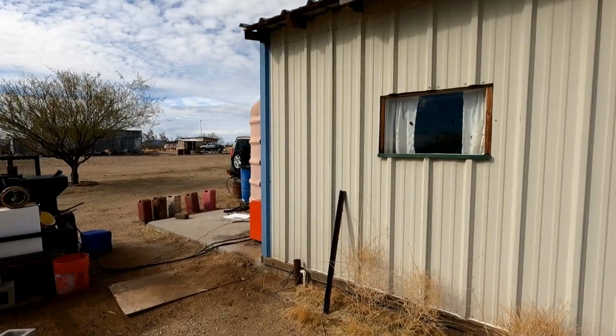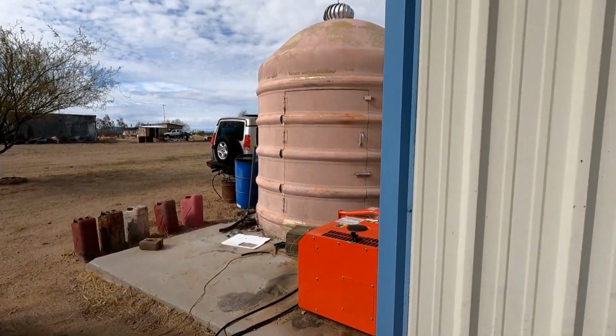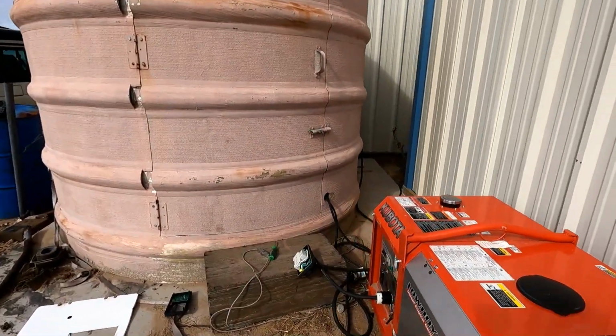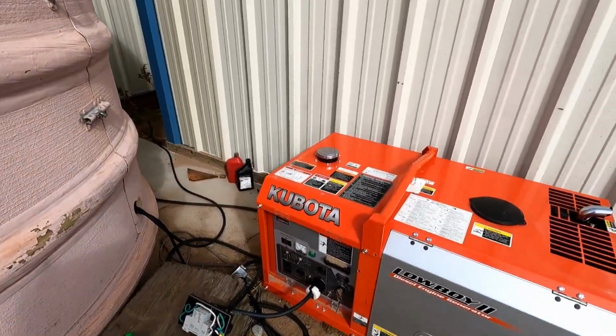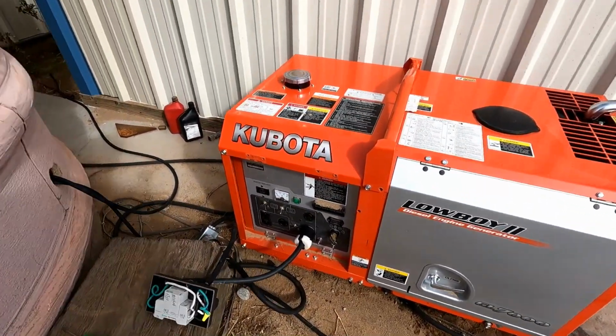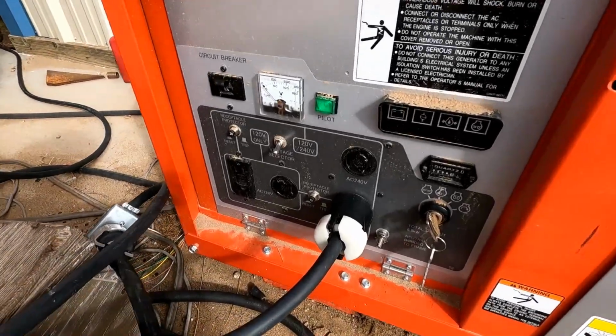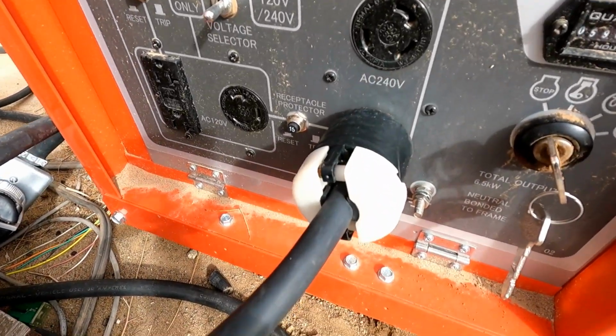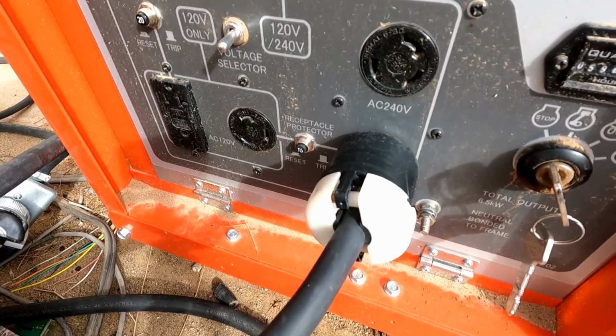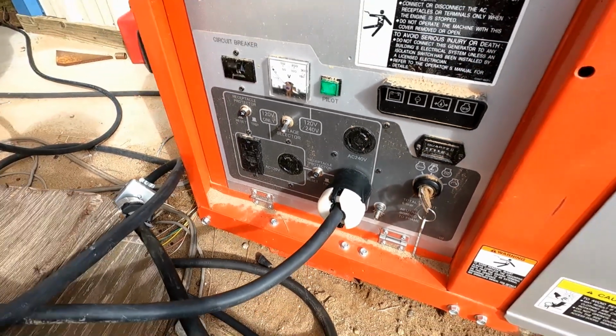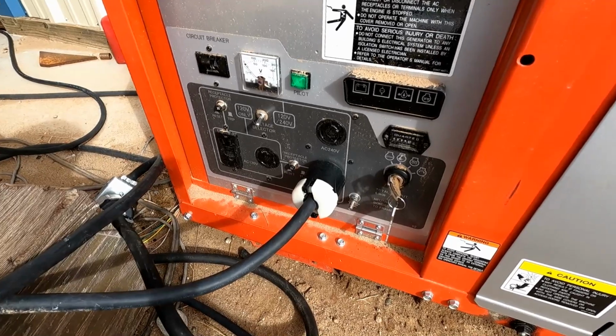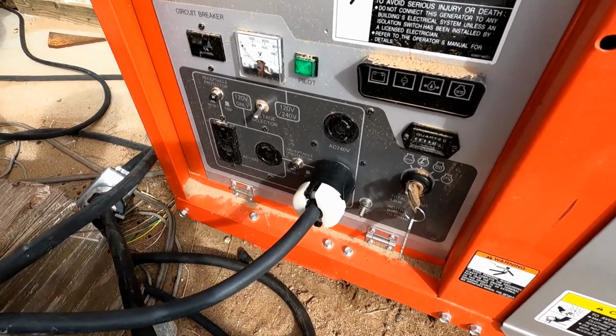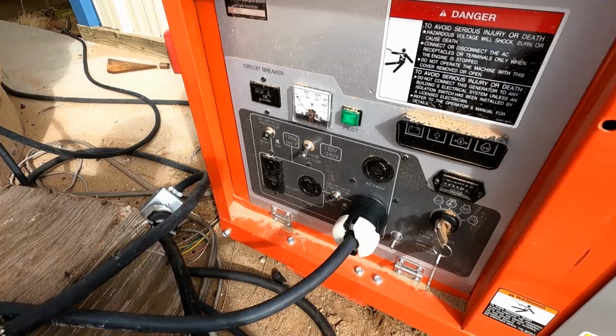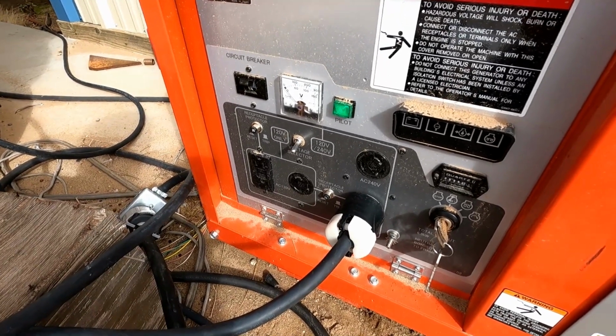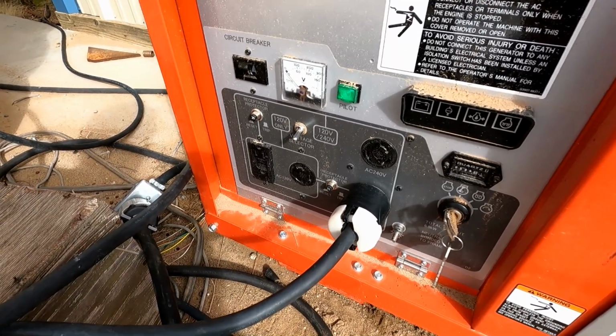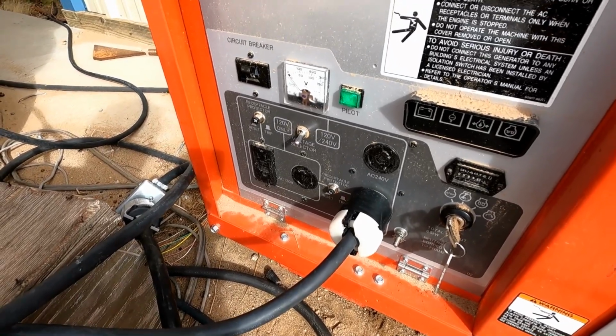And now we've got 150 feet of cable with high current electrical energy contained within it. And that energy is going to want to go somewhere, such as back into the generator. Now, us engineering types, we call this inductive kickback. You civilians probably call it a surge or something of that sort. And the result of this is that it induces a very high peak voltage back into the generator.